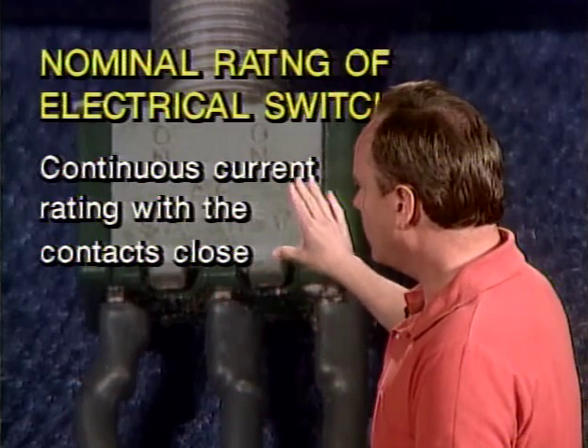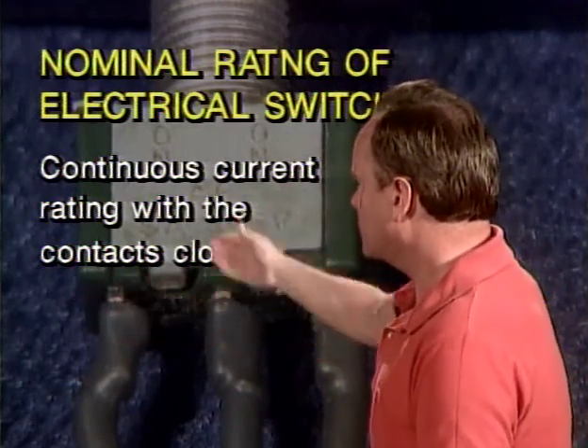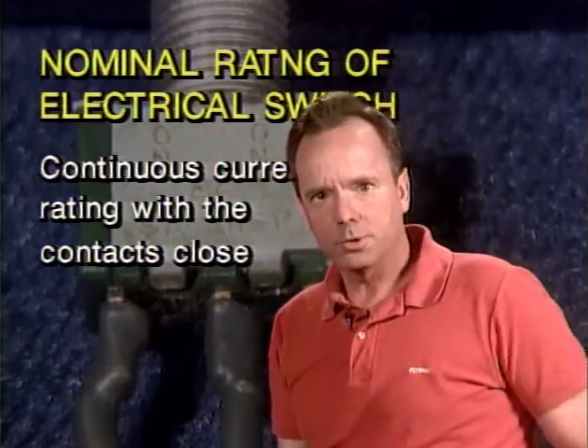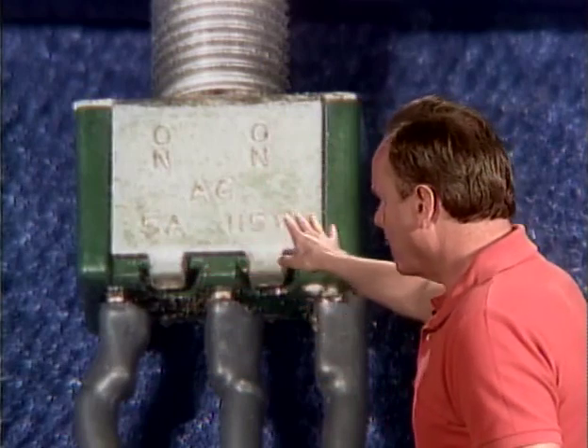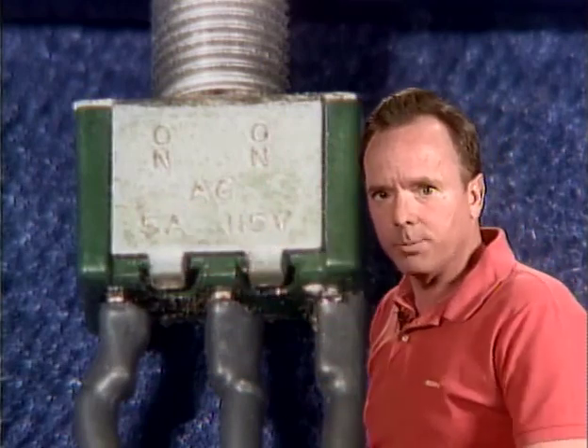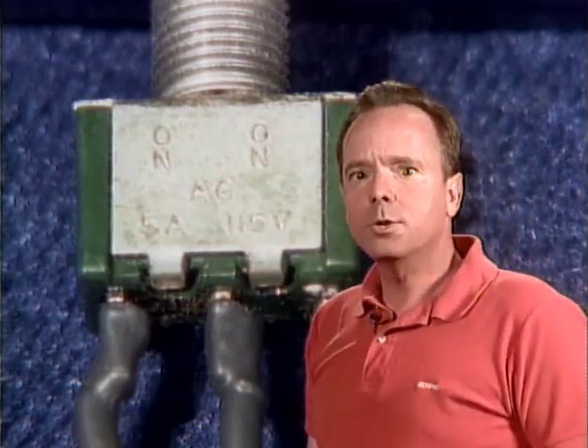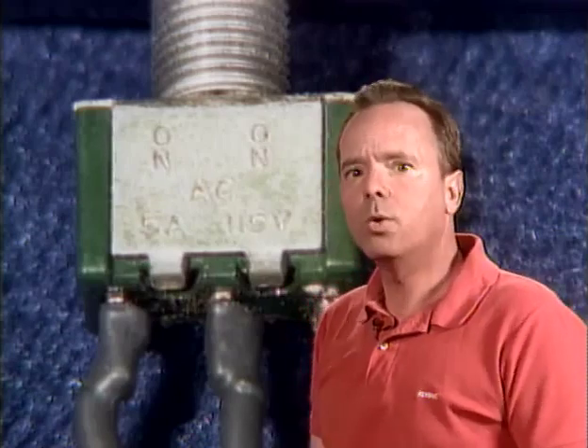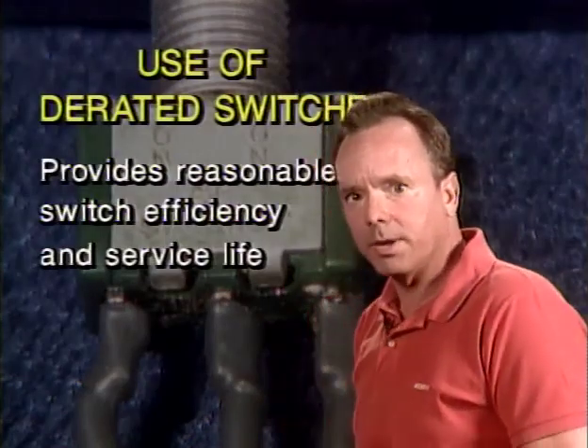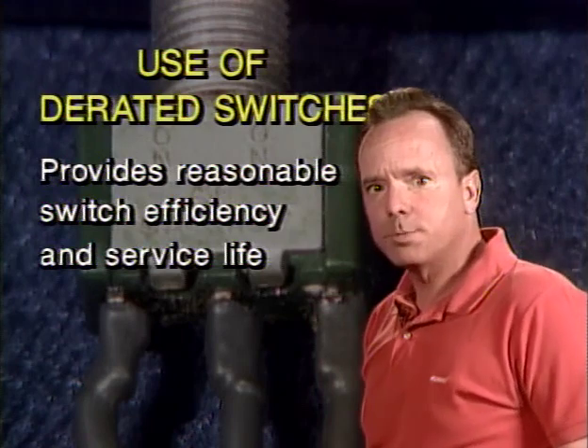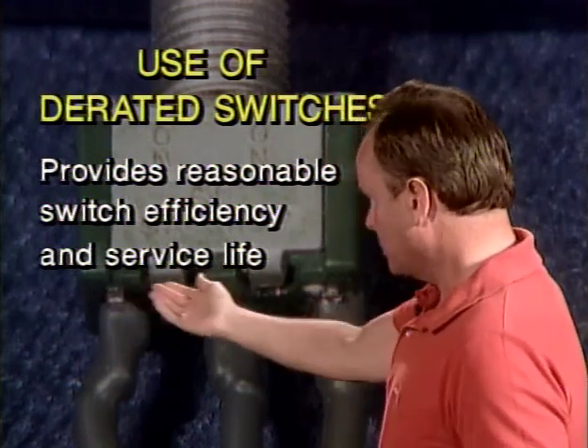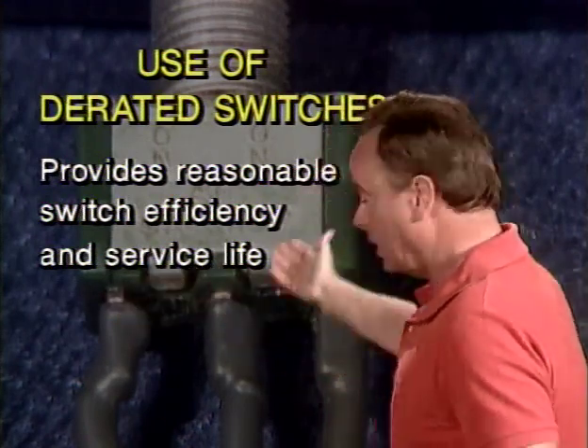That's what you can do continuously with the contacts closed. That's called the nominal rating of an electrical switch. Now, the nominal current rating of an electrical switch is normally stamped right on the switch housing, so you'll see it stamped right on the switch somewhere. Now, the good idea is the use of derated switches for known continuous load current applications, and that provides reasonable switch efficiency and service life. Just like derating an engine, you can derate a switch.